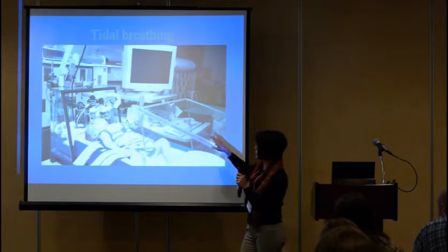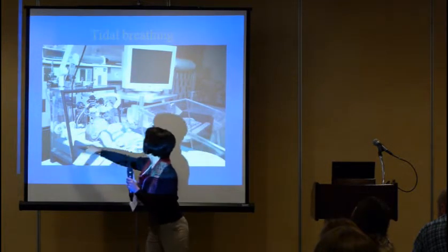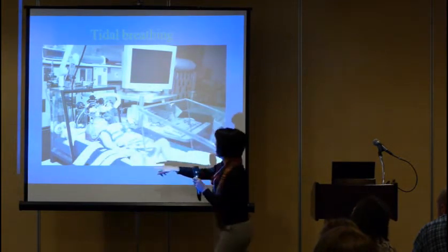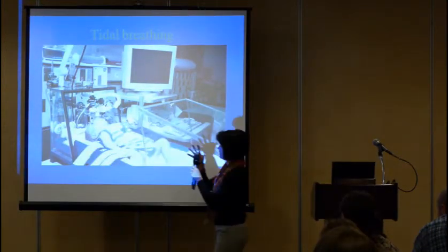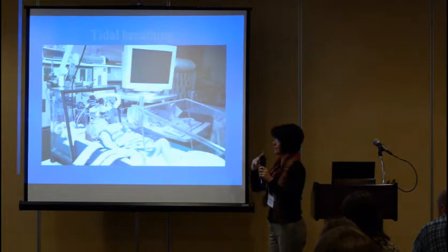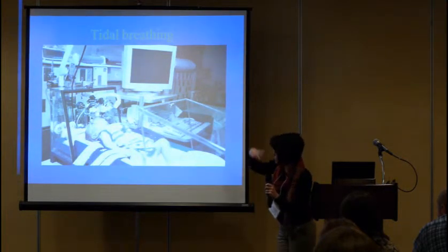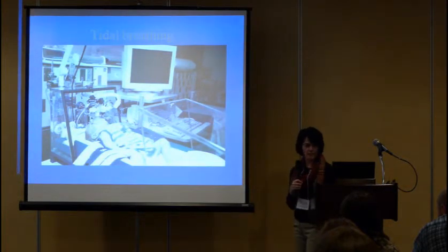When you do the lung volume part, this part just slides and makes a seal here. They're always breathing through this, so this is where the oxygen and air and everything comes in. So even though the box is sealed, they're still breathing through air that's coming through that circuit.